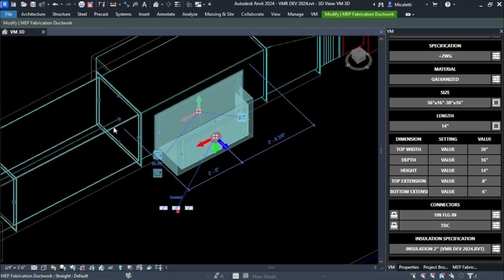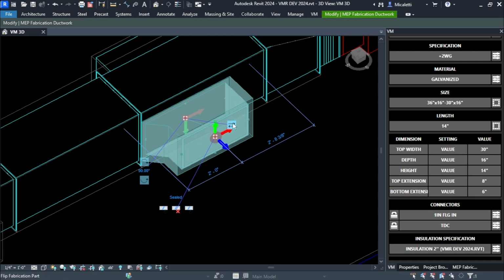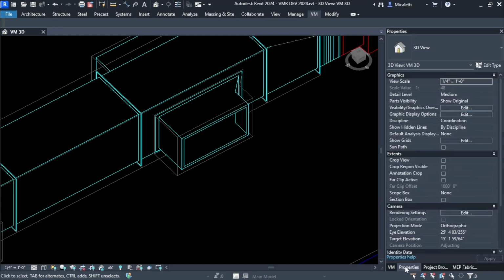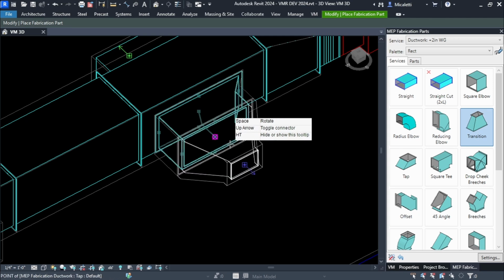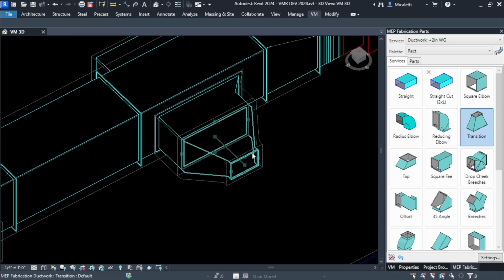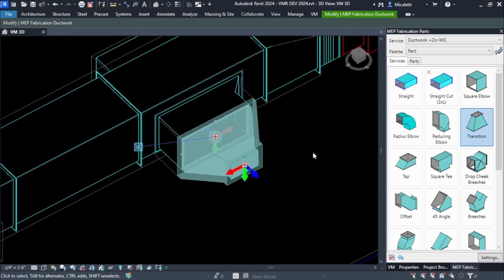Which way is up just depends on which way this shoe tap is facing, which is fine for the tap. It's not an offsetting fitting, so this isn't super important. The problem arises when we go and we put a tap on, or a transition on this. Now this value carries over. It's carried over that idea of up, which is down, which means top flat will be bottom, bottom flat will be top, and lefts and rights are swapped. When you put an offset tag on this, it will still build correctly. It's just not describing correctly or flipped correctly.